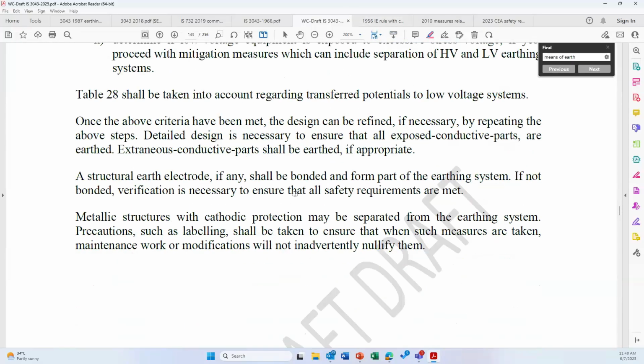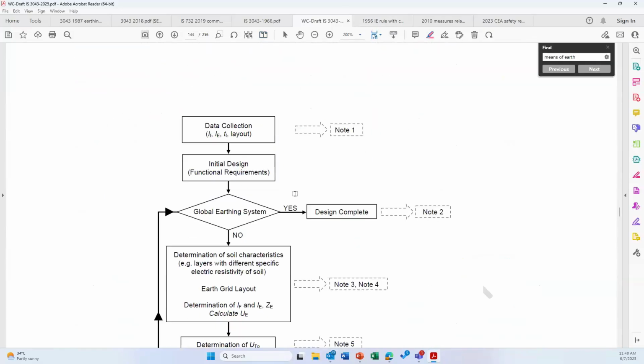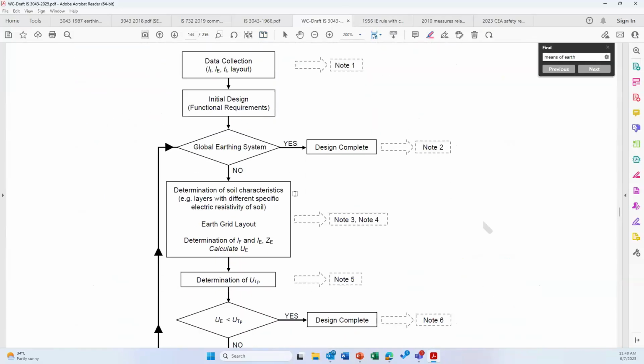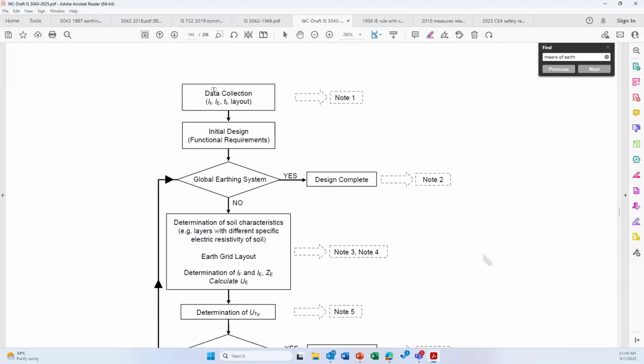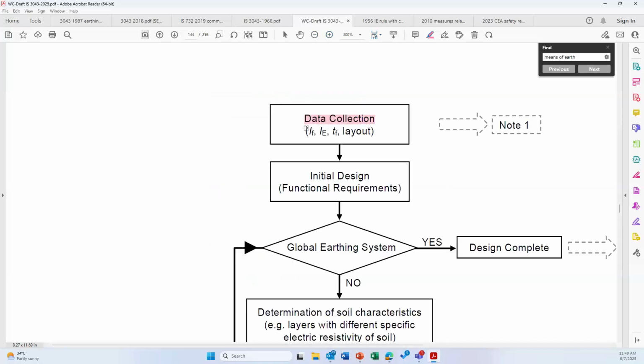Now, if we go to this particular figure, most important, you will be able to find out a table how to make earthing if you have an installation which is more than 1 kV. That means you have 11 kV supply or 33 kV supply, or maybe a transmission distribution substation or whatever, anything above 1 kV, how you should do. Data collection. The data to be collected are IF. IF is the total earth fault short circuit current. IE is the amount of the earth fault current which is flowing through the earth electrode.